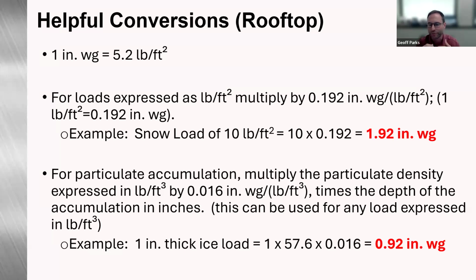So what we're trying to do is, when you're building ductwork that's going to be on the roof, it needs to handle snow loads, ice loads, wind loads. This is a way to take those loads and convert them into inches of water gauge. So I'll wrap this all up on the next slide, but this way you can stay within the HVAC duct construction standards and not have to go into, say, the rectangular industrial for exterior loading.